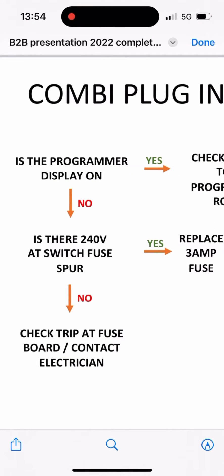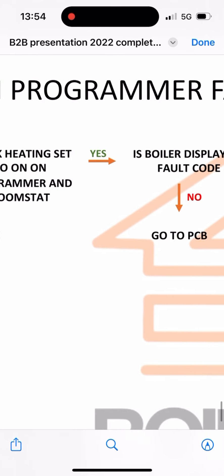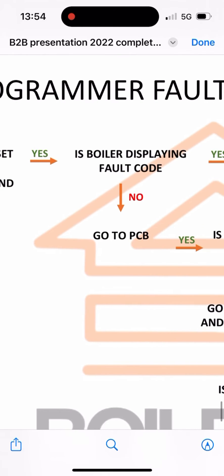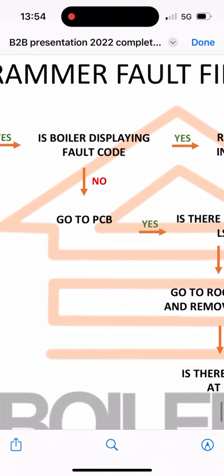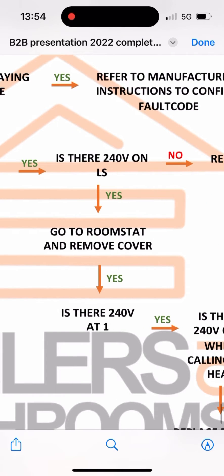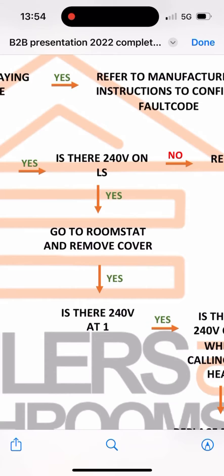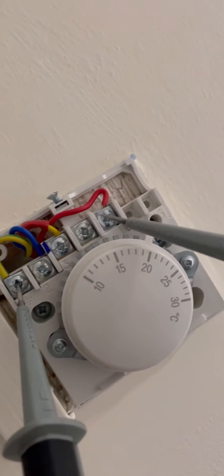There's a programmer display on, yeah. Check the heating's calling - it's an MT10 so there's no display but you can hear it ticking. Is the boiler displaying a fault code? No. Go to the PCB, whip the back off. Is there 240 on LS? Check F to LS - yeah, 240.